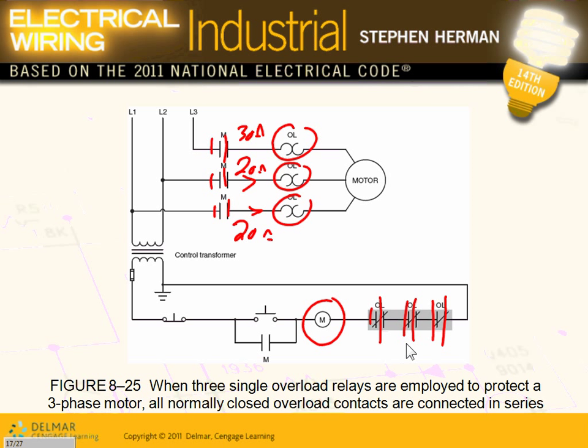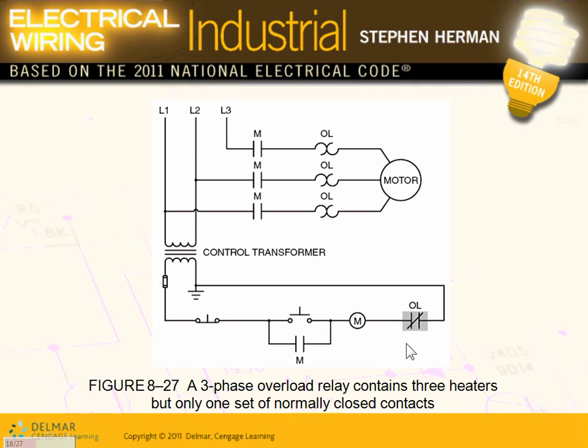You would never be able to understand control if you don't understand that little schematic. This is a three-phase setup — any one of these heaters can heat up and open the same contact. They're all in each phase; any one of them senses a higher flow of current, it pops the contact open. And in a case like this, it will de-energize the magnetic contactor.